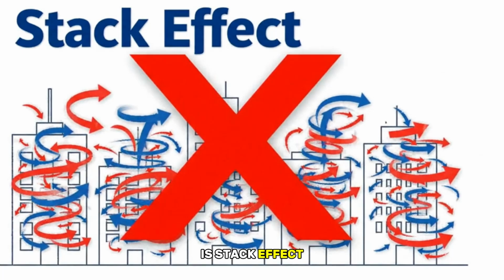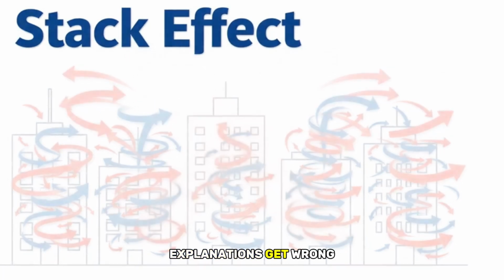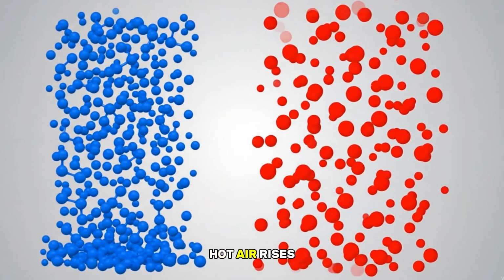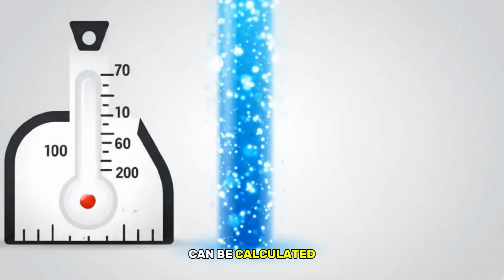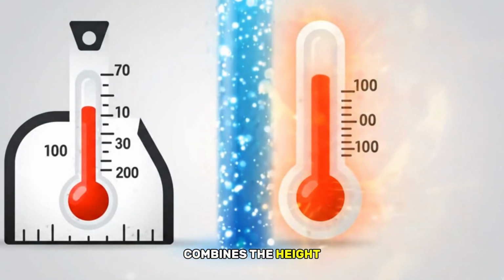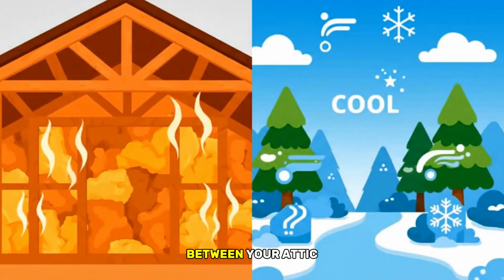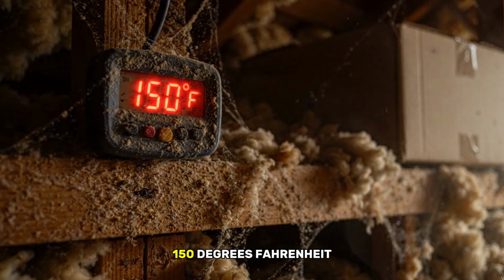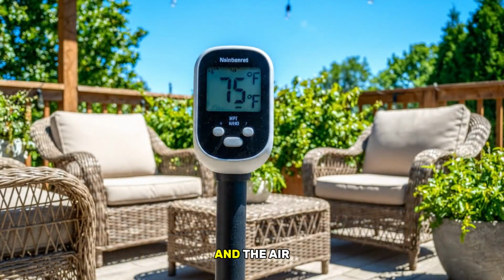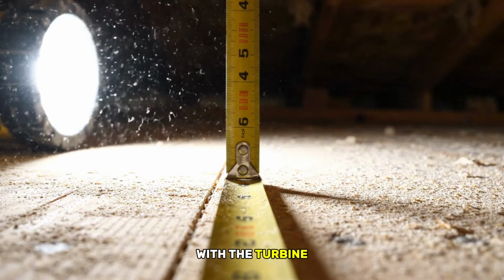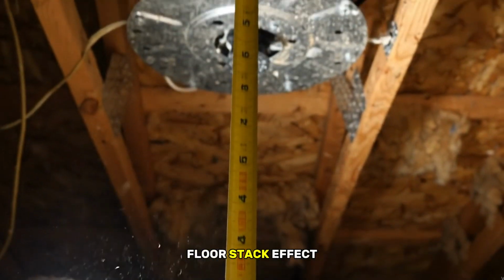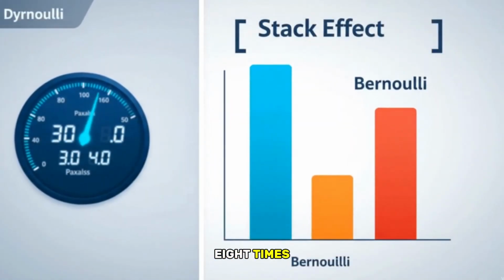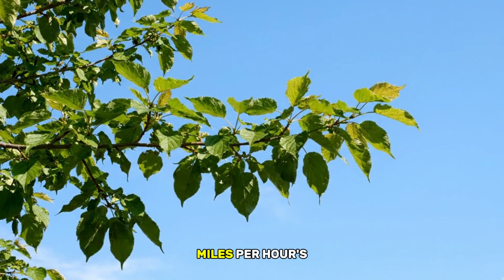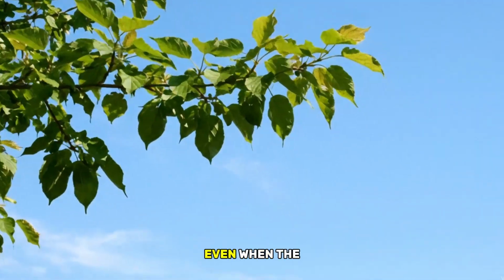The second force is stack effect, and this is the one most explanations get wrong. Stack effect is what happens when hot air rises because it's less dense than cold air, and the pressure that hot column creates can be calculated exactly. The formula combines the height of the column with the temperature difference between your attic and the air outside. Say your attic is sitting at 150 degrees Fahrenheit and the air outside is 75, with the turbine mounted 4 feet above the attic floor. Stack effect alone generates between 3 and 4 pascals of pressure. That's 6 to 8 times stronger than the Bernoulli effect from a 10 miles per hour wind, which means the turbine works even when the wind is dead still.